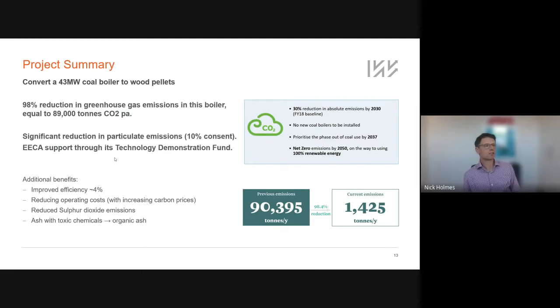Fonterra is obviously a very large dairy milk producer in New Zealand. They've got, I think, up to about 30 spray dryers across New Zealand. So they're obviously a major player, but a lot of boilers in their portfolio. A lot of their older boilers are coal. Fonterra have obviously got some commitments to lower their emissions. So a 30% reduction within the next 10 years, or 9 years now. Obviously they've committed to no more new coal boilers and to phase out coal by 2037, to get to net zero. So this one particular project, a 43 megawatt boiler, would give a 98% reduction in greenhouse gas emissions. So a massive reduction to tick off this one boiler.